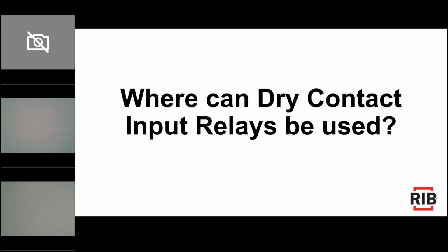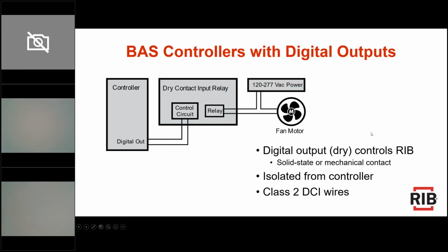So where can dry contact input relays be used? I want to use this webinar especially to show some different applications of the dry contact input relays across the whole board of the options that we have. So the first one, of course, the BAS controllers, building automation system, those controllers with digital outputs. So if it's a controller, whether it has a solid state digital output or mechanical contact digital output, and when I say digital output, that just means it's either on or off, open or closed.